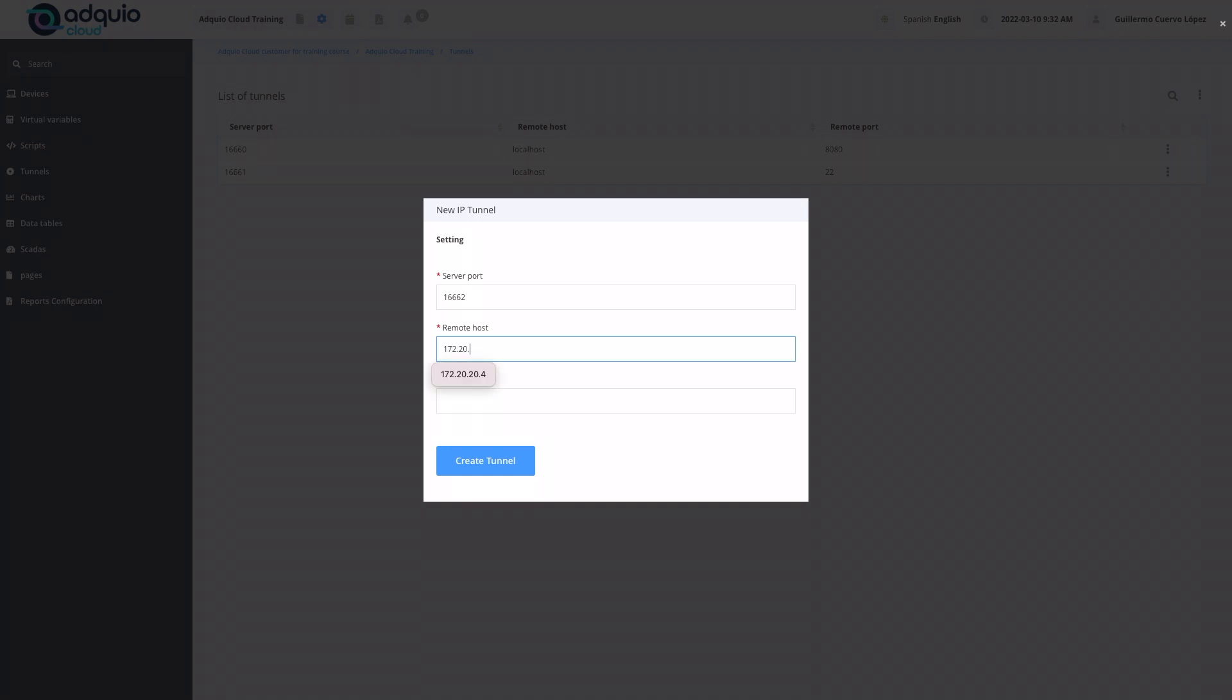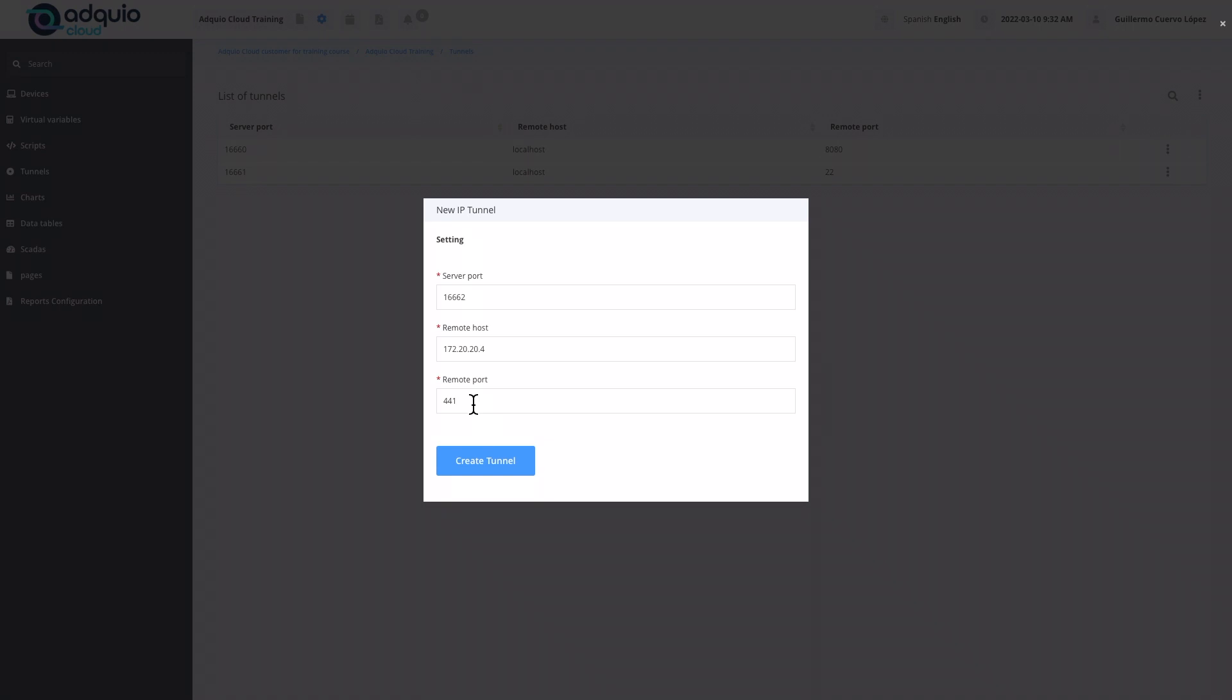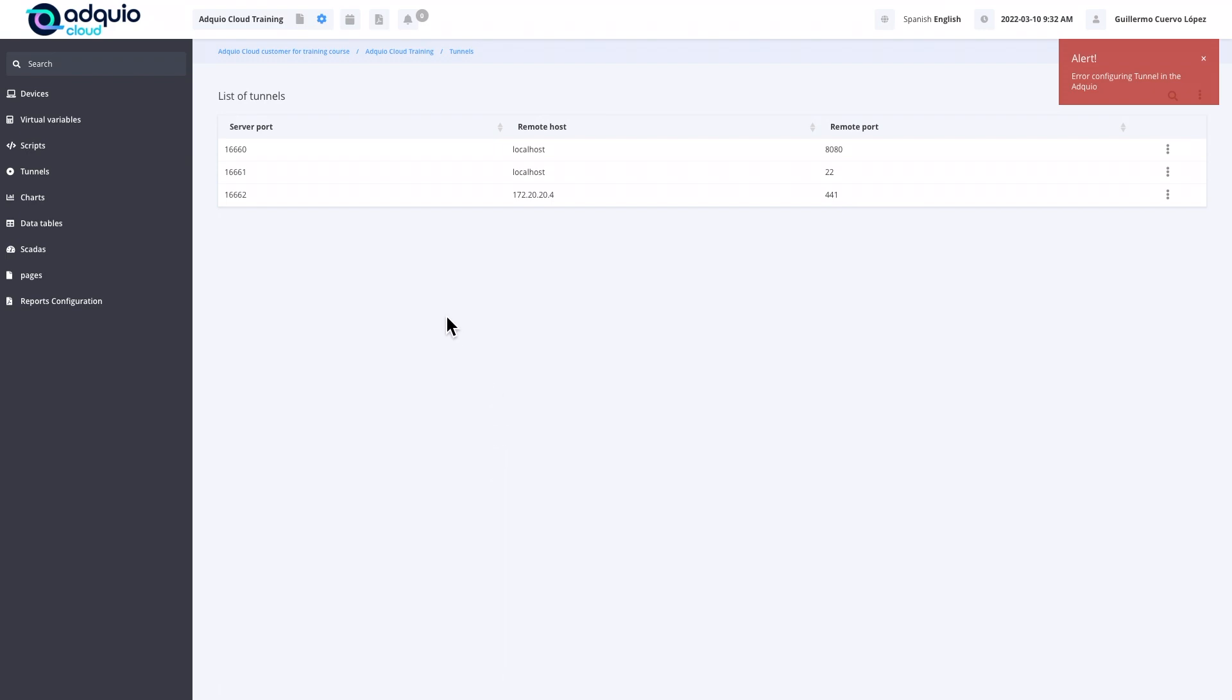We are going to give it a new tunnel. We would have the 16662, 16663, and the 16664 free. Remote host is the IP address of the PLC to which we want to access from our local office, the IP address that it has in the electrical panel. We will put it, for example, 172.20.20.4. Finally, we must indicate the port of that device through which we are going to access. Normally, the brand of the automaton will already indicate which port is the configuration port for your device. We are going to put 441 for example. With this, we would already have this tunnel working. The moment we create a tunnel, it will create it in real time and we will have our office access the port.